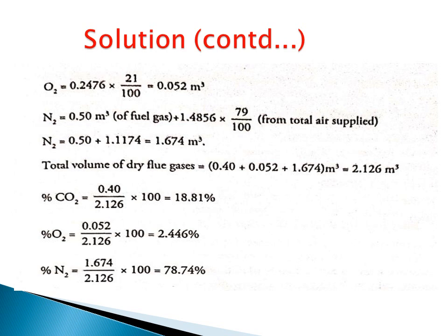Remember one thing, when the numerical contains excess air, then oxygen will be there in the flue gas. When it does not contain excess air, then the flue gas will not contain oxygen. This is important, and all of you should remember this.